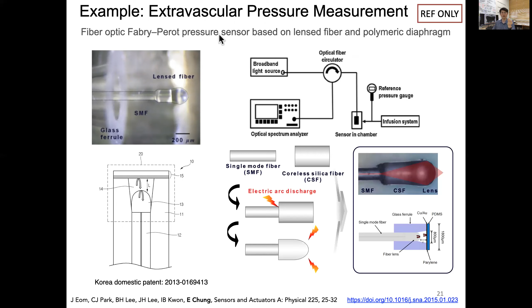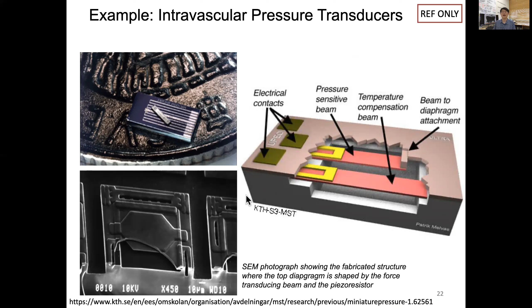That's an example of a very fine extravascular pressure measurement system. You could potentially use it inside the body. Another is the intravascular pressure transducer, which is very, very tiny, as you see next to this coin. Tiny sensors can be put directly inside the vessel to measure pressure. This is a diagram showing the pressure-sensitive beam and compensation control, and the electron microscope image shows the fabricated devices.